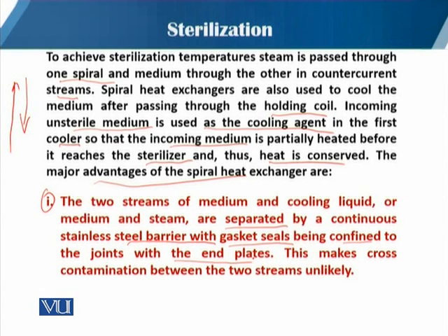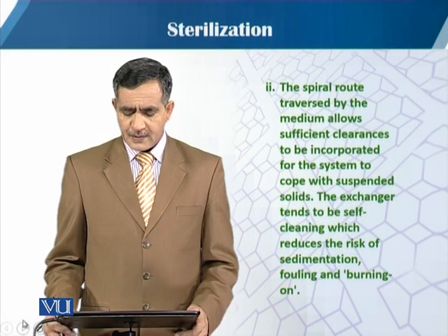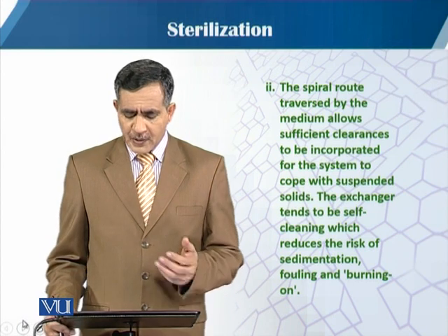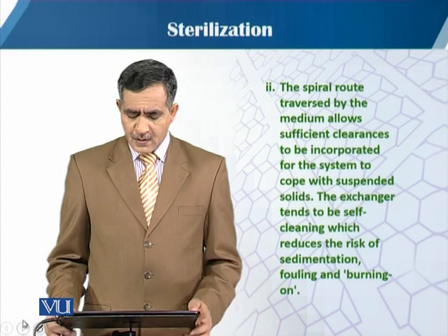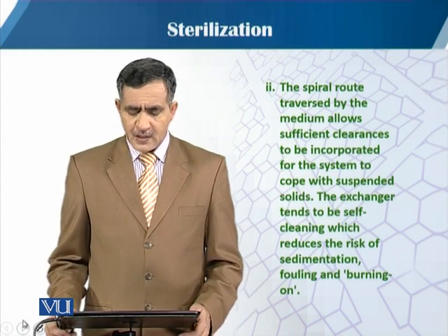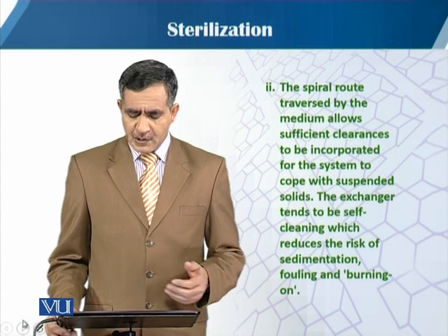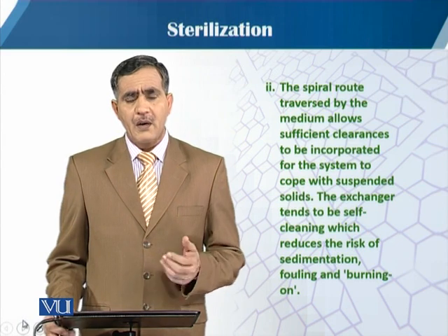As concerned, the spiral route traversed by the medium allows sufficient clearance to be incorporated for the system to cope with the suspended solids. The exchangers tend to be self-cleaning, which reduces the risk of sedimentation, fouling and burning-on.